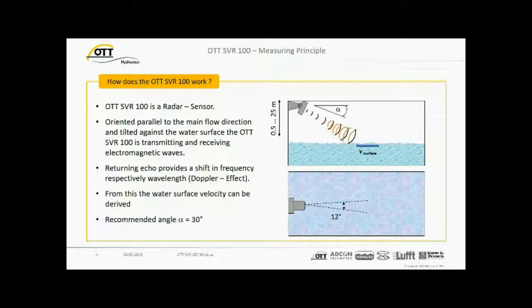How does the sensor work? This is not difficult, it's easy. It's a Doppler sensor. The SVR 100 is a radar sensor. We are operating with electromagnetic waves. So we orient the sensor parallel to the main flow direction. We tilt it against the water surface by an angle of recommended 30 degrees. And then it's transmitting and receiving electromagnetic waves. The returning echoes provide a shift in frequency, respectively in wavelength. This is the so-called Doppler effect.